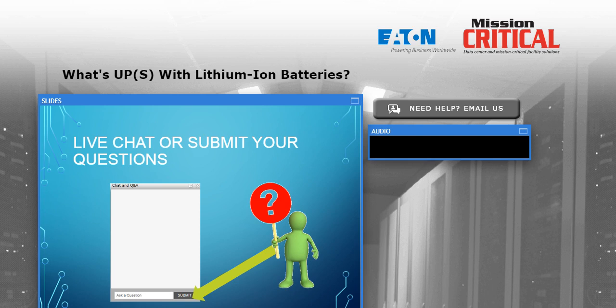But talk to your UPS vendor, and if there's a question they don't know, they can communicate directly with the battery vendor and find out the latest information for you. It's a good idea to do that frequently, because one of the things we've noticed over the last two years especially is these regulations are changing sometimes almost monthly in terms of limits and what's allowed and not allowed. So the answer may change over time, especially in these first few years of UPS deployments.